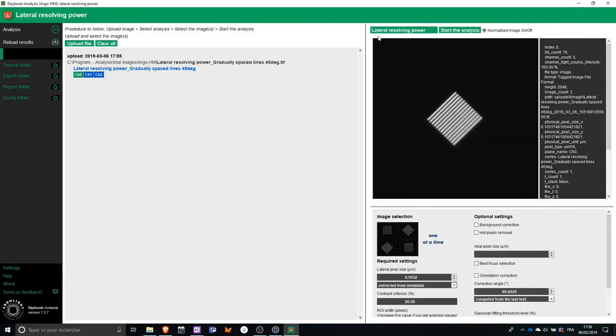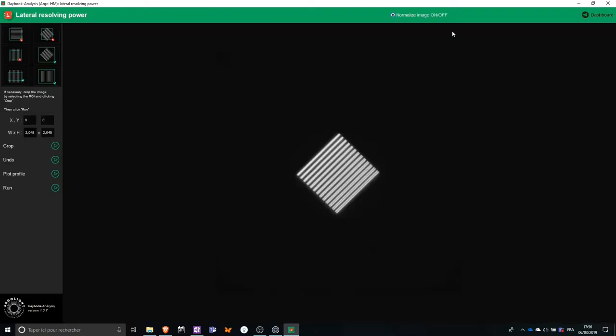For the lateral resolving power test, I need a line, a square line pattern, so I can start the analysis. The final step is the ability to crop the images if you have several patterns in the field of view. It is not the case here, so I can directly click on Run.